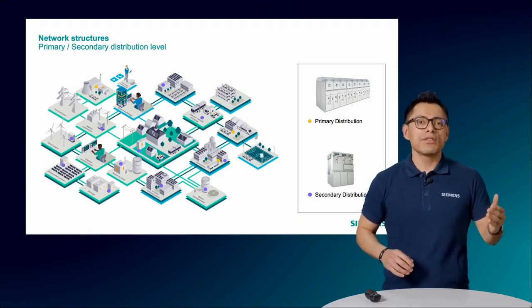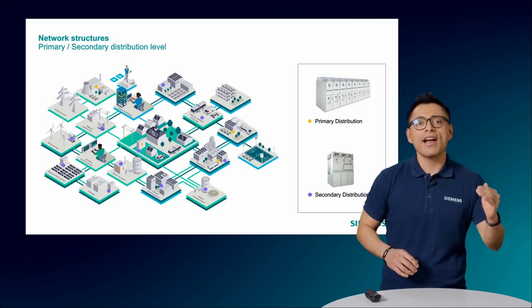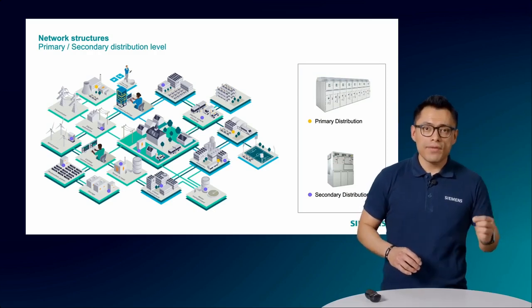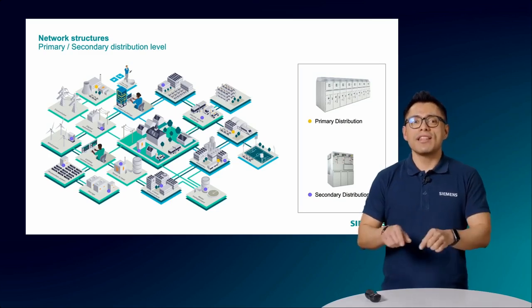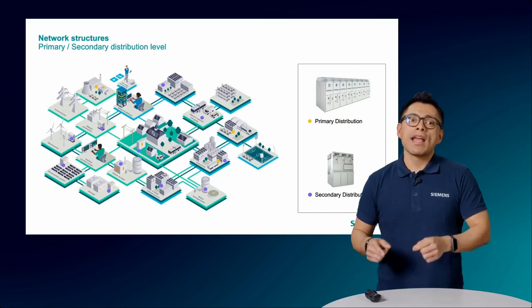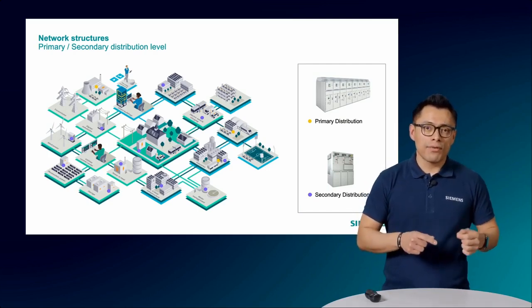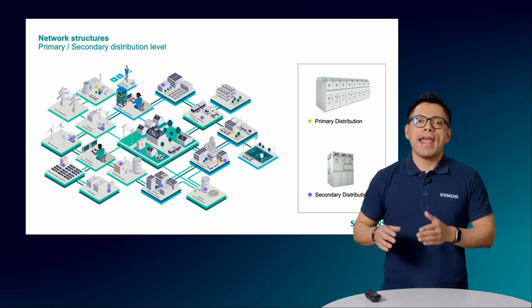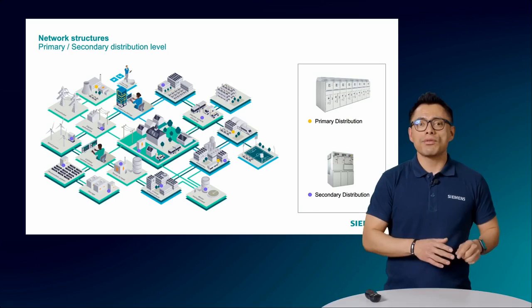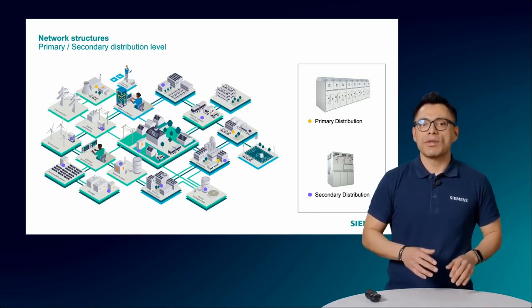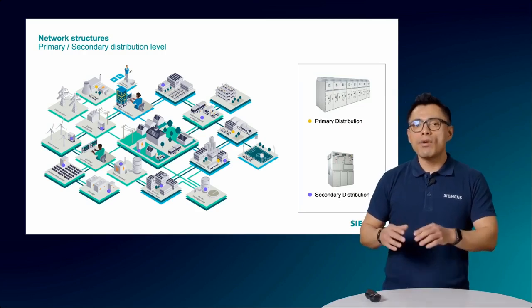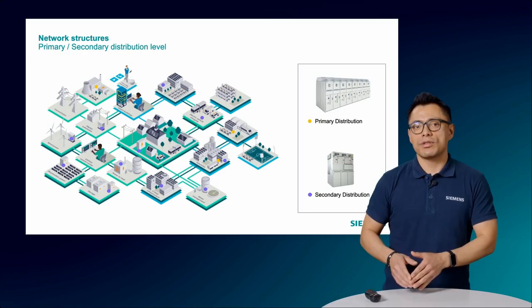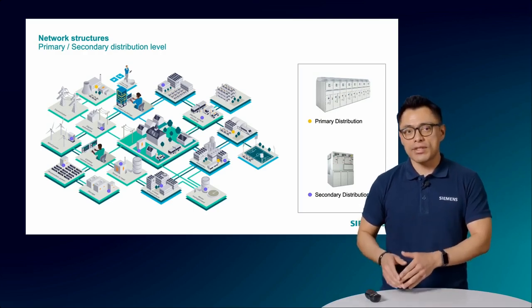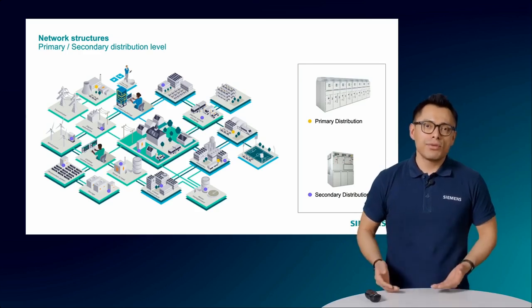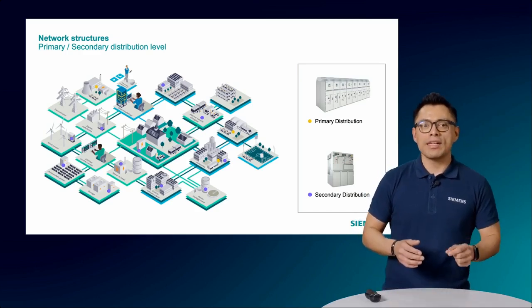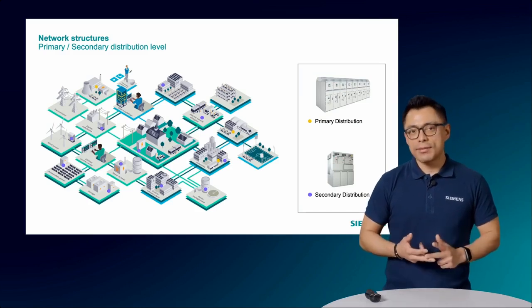Primary distribution is typically known for carrying higher current and withstanding higher short-circuit values. It is also used to deliver power from main substations to several distribution substations closer to the consumers. It is also suitable for delivering a large amount of energy for industrial consumption. And secondary distribution is better known for carrying lower currents and withstanding lower short-circuit values. It is used to deliver power from the distribution substations to the final consumption, making it suitable for end consumers and applications. Primary and secondary distribution work together to ensure that electrical power is delivered efficiently, safely, and reliably.